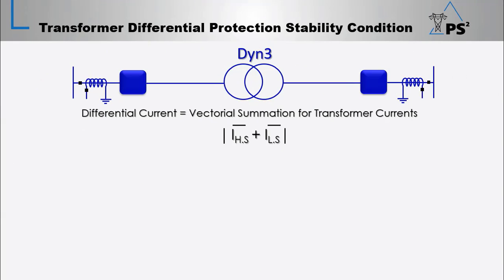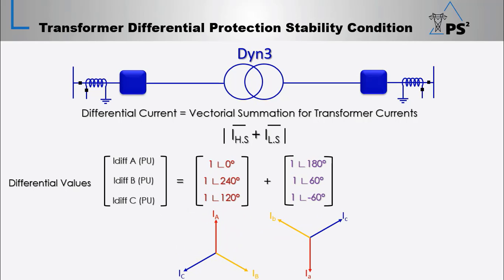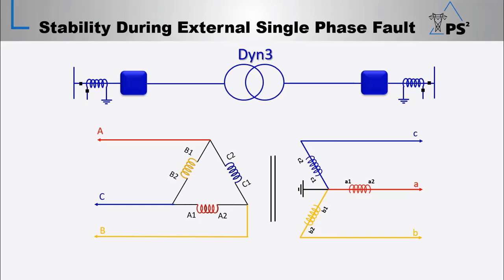Now, as the differential current calculation equals the vectorial summation of the transformer per unit currents, the differential current will be 0, which indicates a stability condition. Now, let's discuss the stability during an external single phase fault.